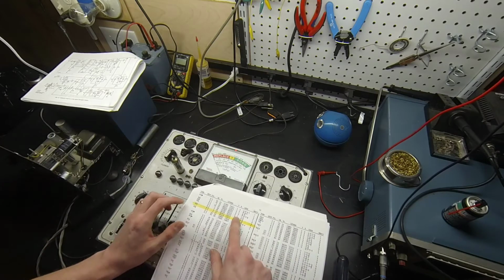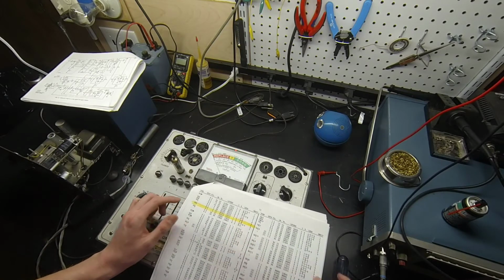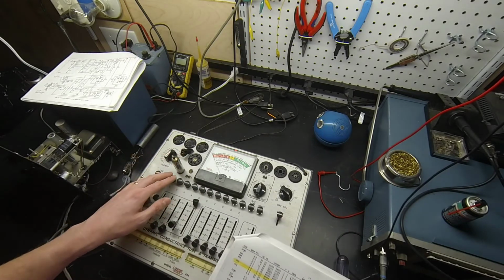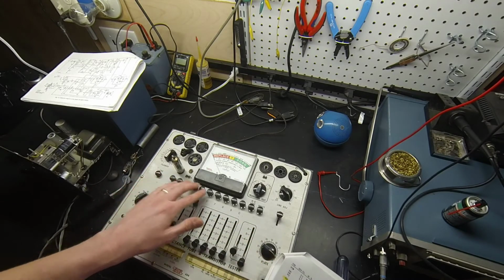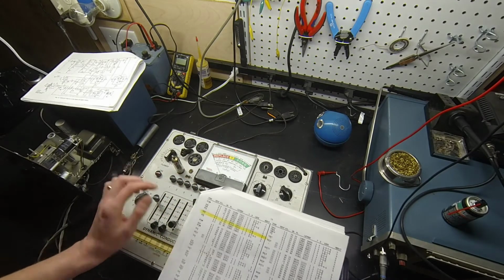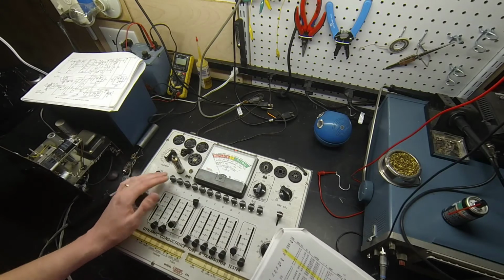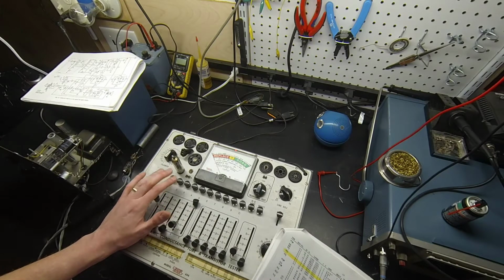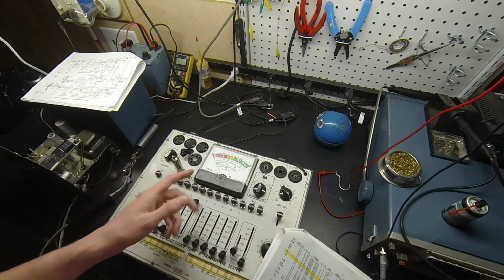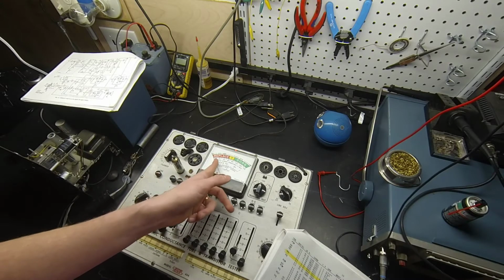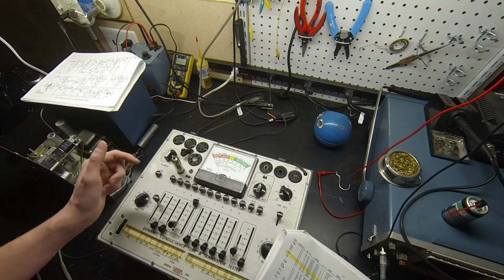But basically, once you've got everything set up, you go through and check for leakages, any shorts within the tube, using the different push buttons according to your chart, to see if anything is shorted, or in this case they're calling it 'leak.' If something is shorted, it will peg this needle all the way over.